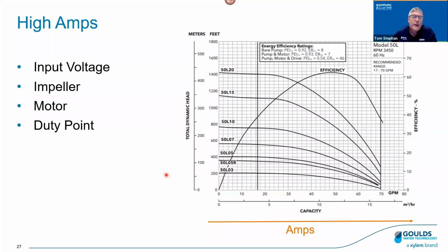Okay, so we measure amperage and we get high amperage or we get low amperage, right? If you do get high amperage, what could that mean? It takes us one step closer, but it could be that our input voltage is off, not within that tolerance window. On the impeller side, maybe that impeller is dragging. Maybe there's some rub, and that's going to create some higher amperage. Maybe the motor itself is starting to go bad. The insulation of the motor is starting to break down.